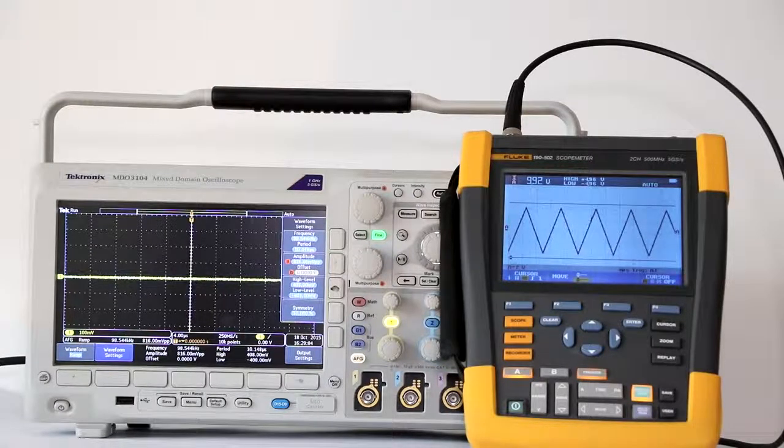To do this, it is best to toggle off the Fine button in order to move faster. Once again, notice that the period, as shown in the Fluke display trace, changes for a second or so until the auto range feature kicks in to size the displayed waveform to fit the screen. The value in the cursor readout remains true to what is coming in.